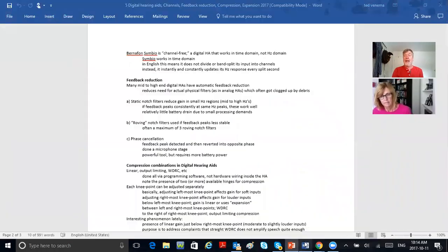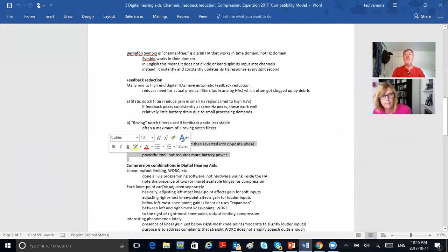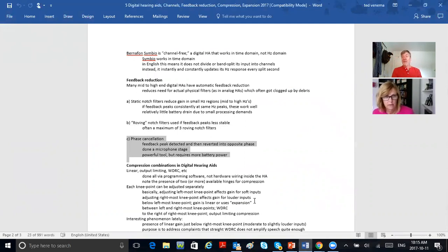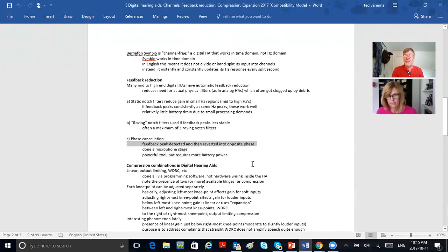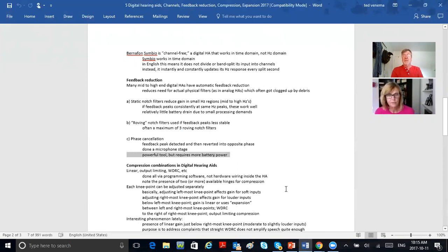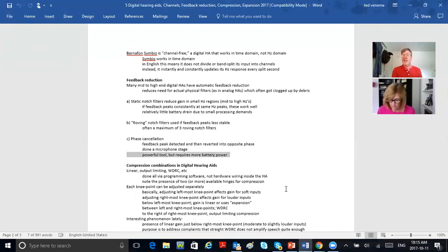The third and main way to prevent feedback used today is phase cancellation. The hearing aid detects at what frequency the feedback is taking place, then produces that frequency in opposite phase, so the feedback is canceled. Feedback peak is detected and then reverted into an opposite phase — done at the microphone stage. It's a powerful tool but requires more battery power.